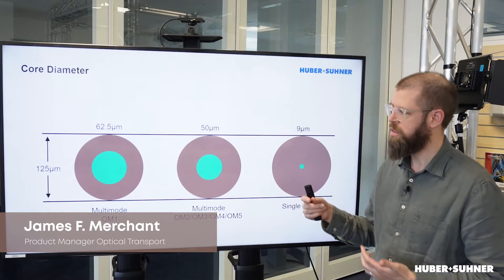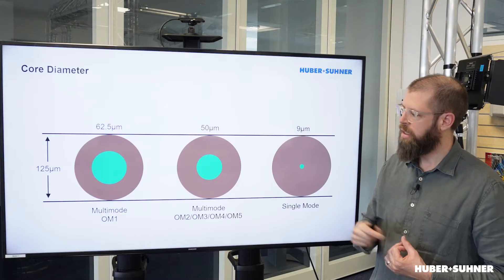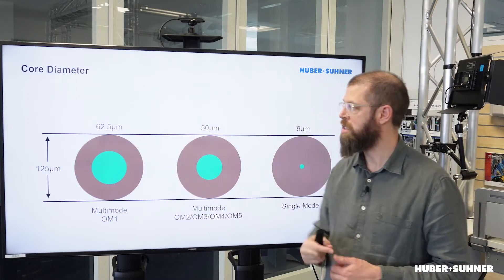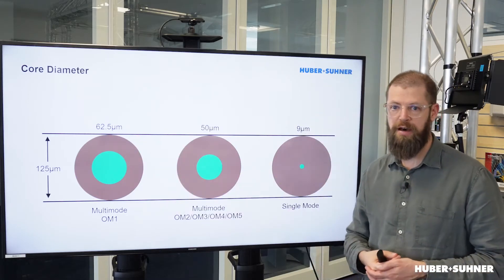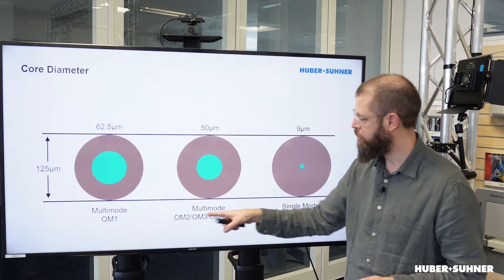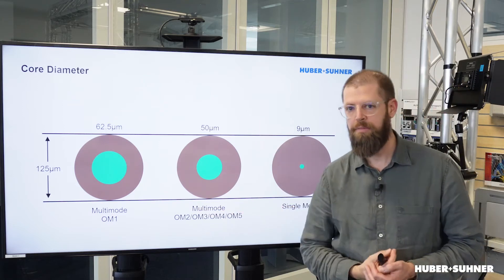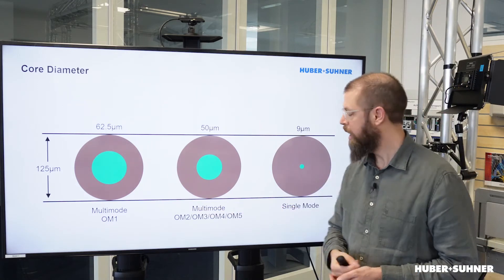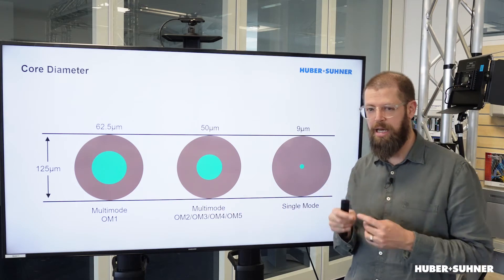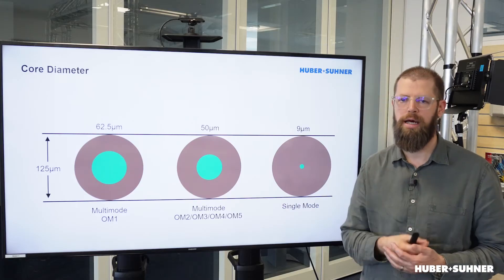The most obvious difference is the core diameter. For multi-mode OM1, we've got 62.5 micrometers. For OM2 up to OM5, we've got 50 micrometers. And for single-mode, we've got that teeny tiny 9 micrometer core diameter.